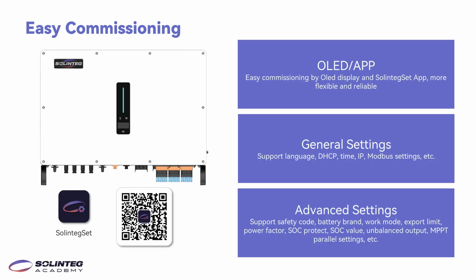For our inverter, it is very easy to do the commissioning. You can just operate on our OLED display or in the application: scan the QR code, download and install it on your phone, and start to check the data and do the configurations. On the OLED display, there are 2 kinds of settings. One is general setting, which supports language, the IP and Modbus setting, or DHCP settings. For this setting, you don't need to input the password.